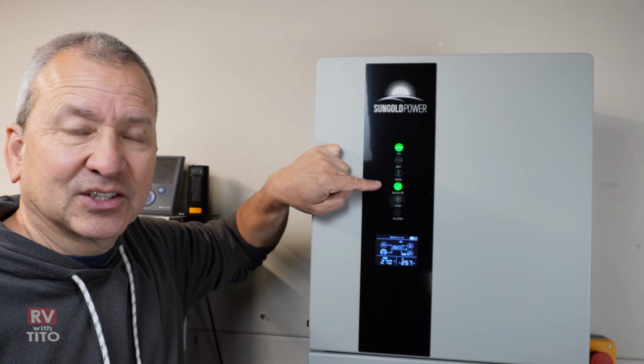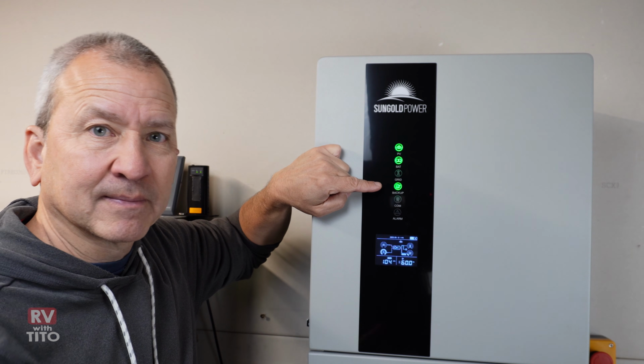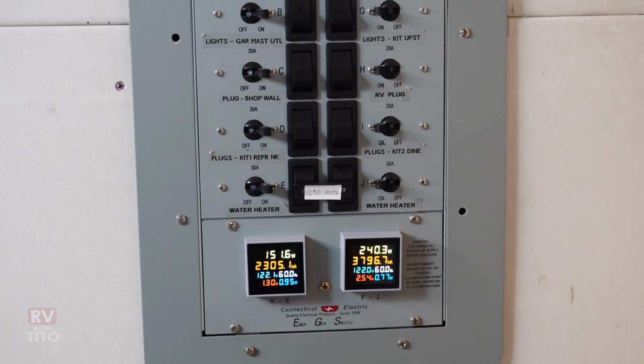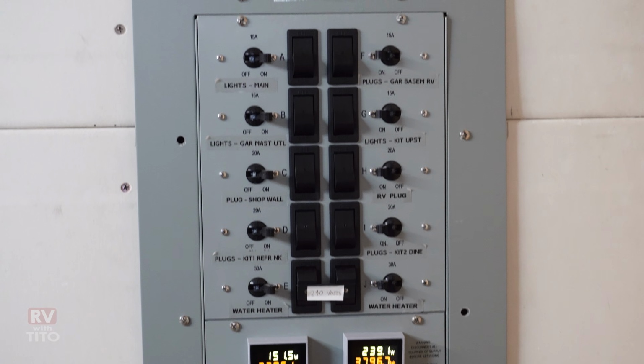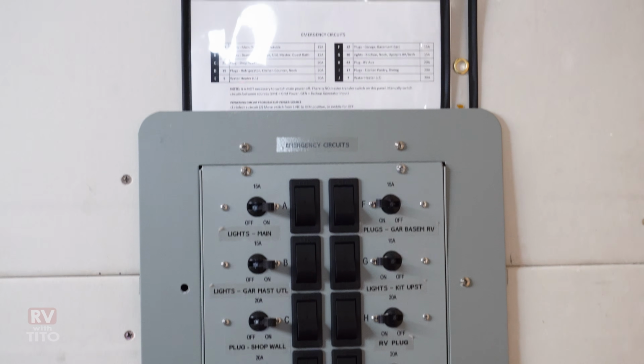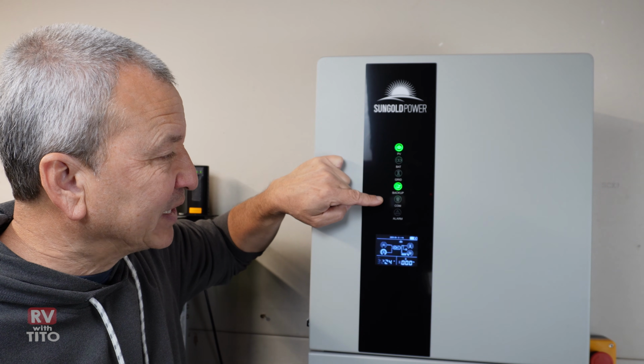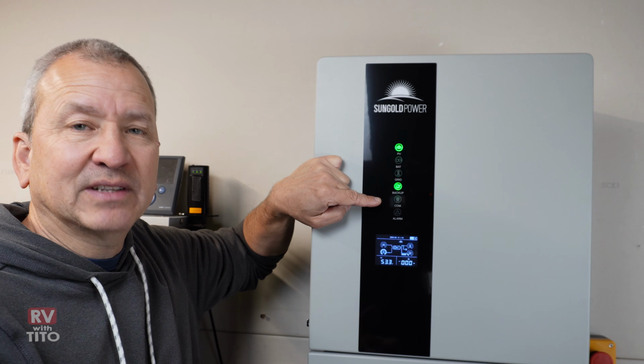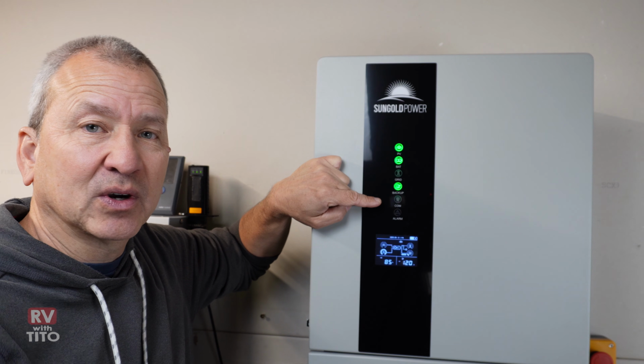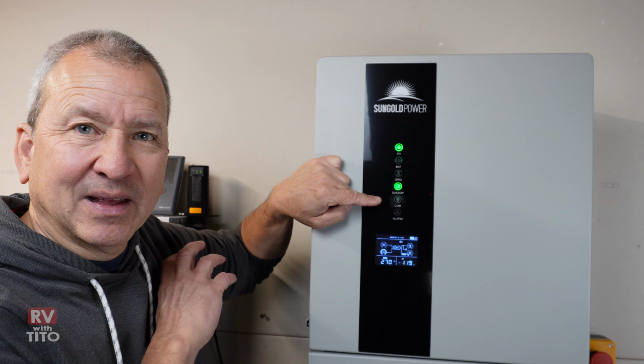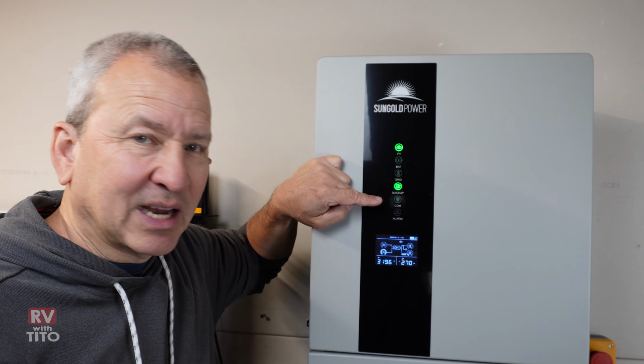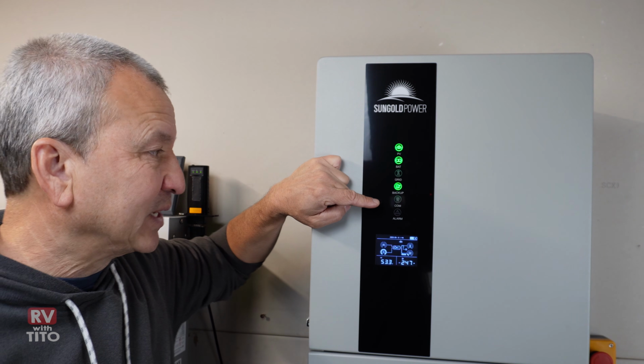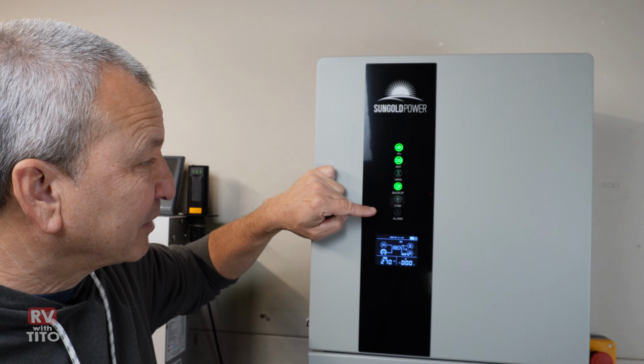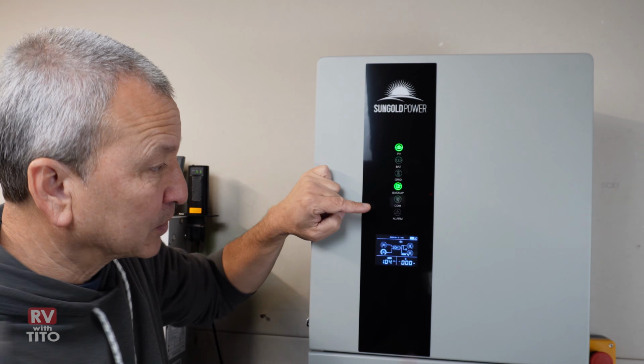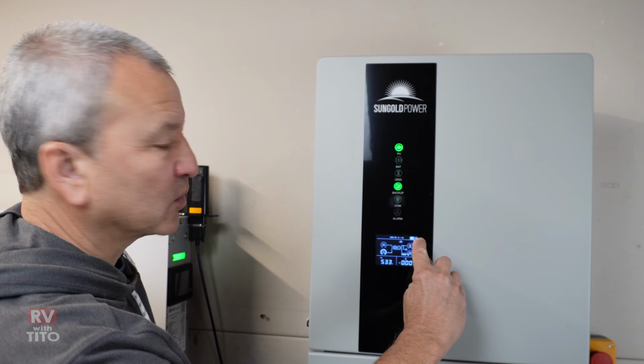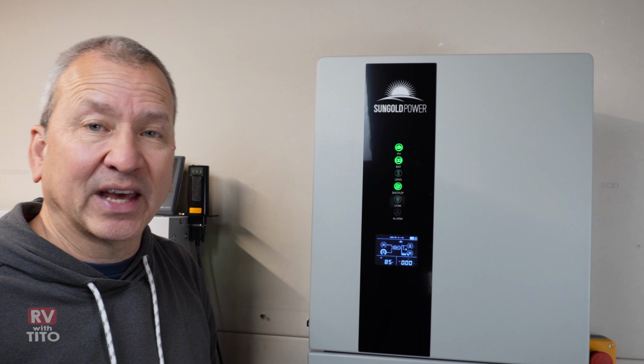The backup indicator shows our backup loads, meaning all the loads I have connected through my emergency circuits panel, which I'll show you real quick. There's also an indicator for when communication is happening, like connecting to our closed loop BMS communication, which I'm not using, but I'll show you what I'm doing instead. This will blink if we have any alarms, and those alarms will show you the actual error or alarm number so you can look it up.